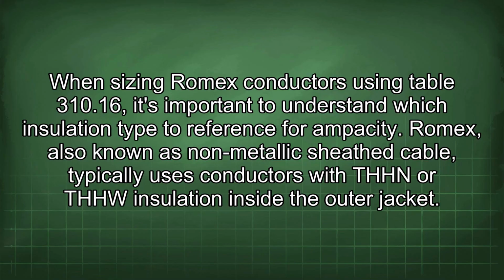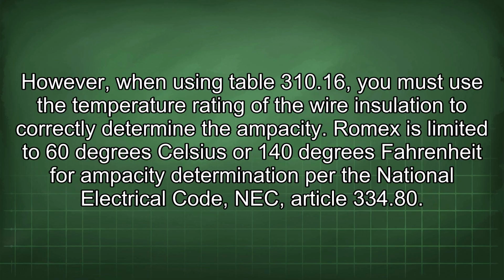When sizing Romex conductors using table 310.16, it's important to understand which insulation type to reference for ampacity. Romex, also known as non-metallic sheathed cable, typically uses conductors with THHN or THHW insulation inside the outer jacket. However, when using table 310.16, you must use the temperature rating of the wire insulation to correctly determine the ampacity.